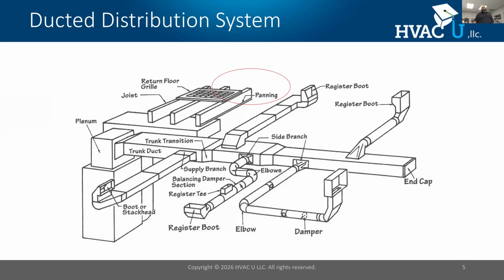In the Midwest, we have basement applications. And what I want you to see here is that the duct system is quite intricate. When we're looking at this duct system, we see that we have various shapes and sizes. These shapes and sizes are often done to accommodate some building construction. So you see how this is right here, kind of oddly shaped. It's flat. All right, that's a wall stack. So the fittings that are designed and specified when a new duct system comes in are really designed to help accommodate building construction. All right, they all have pressure drops and all that kind of stuff. We need to understand that when the duct systems go in.